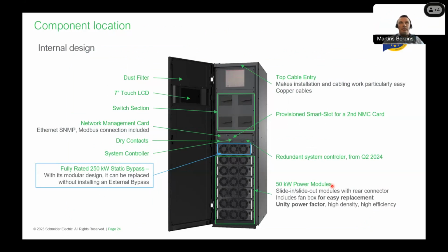Regarding the layout or internal design, this is how the UPS looks when the door is open. We have a dust filter inside the door. As I said, it's for light industrial applications, so this is quite a handy accessory. 7-inch LCD touchscreen display. Then the switch section, right? This is with a 4 switch section. We have this also in the one switch model. The network management card is also integrated with Ethernet, SNMP, and Modbus connections included. We have 9 dry contacts, 4 input and 5 output contacts.